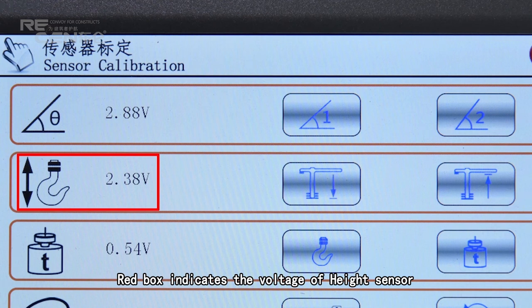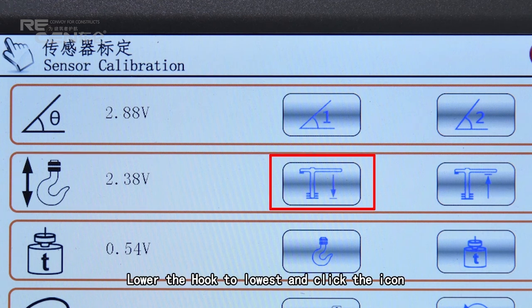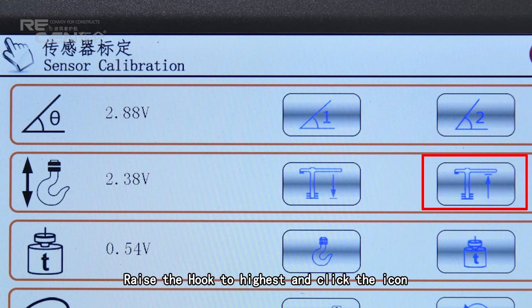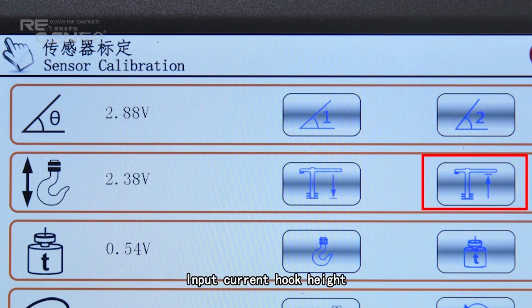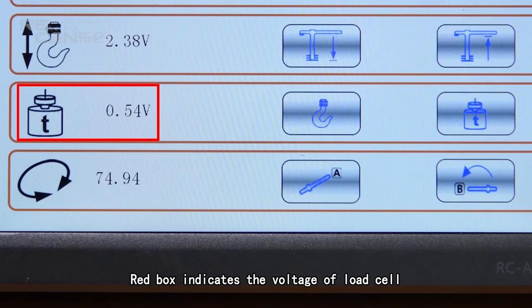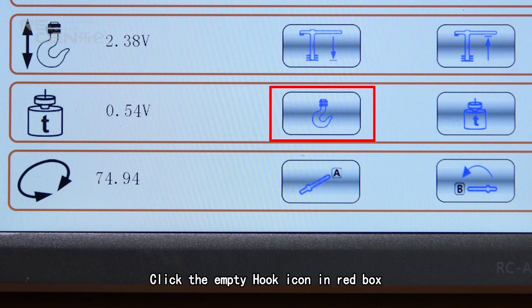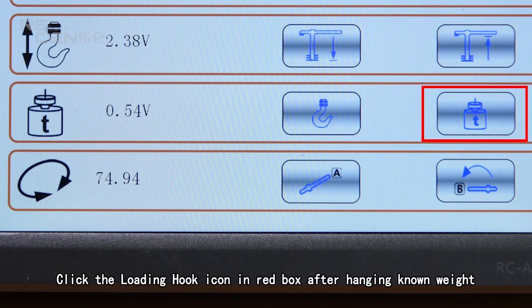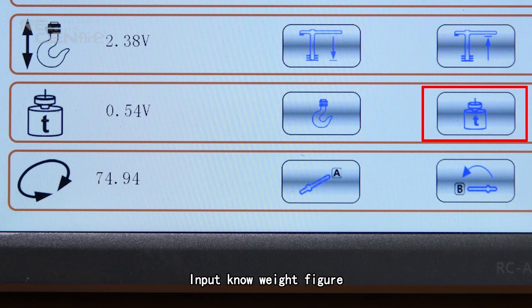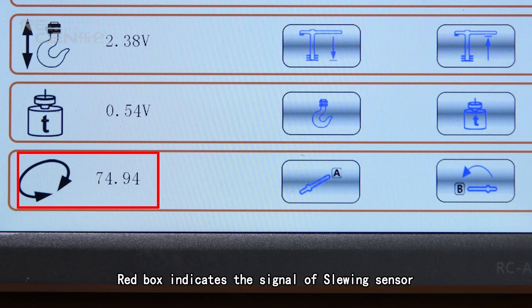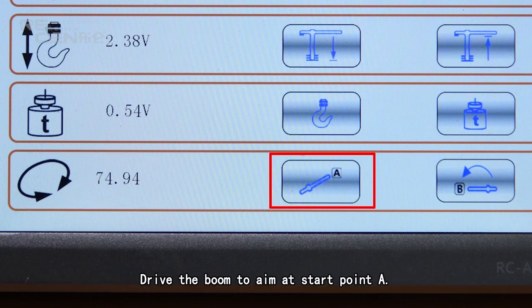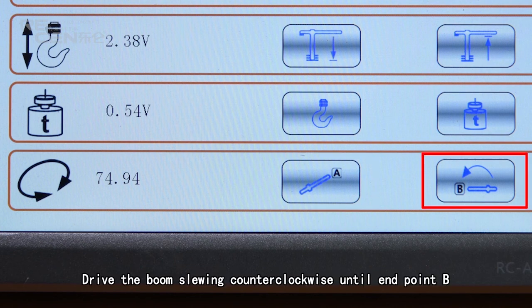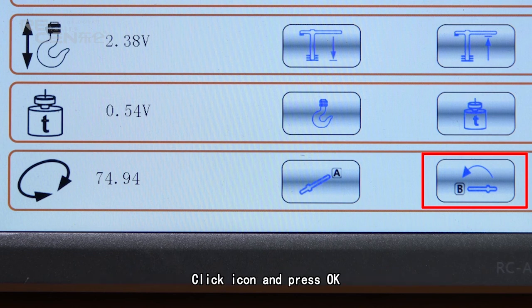The red box indicates the voltage of the height sensor. Lower the hook to the lowest position and click the icon; input the current hook height. Raise the hook to the highest position and click the icon; input the current hook height. The red box indicates the voltage of the load cell. Click the empty hook icon in the red box and input 0. Click the loading hook icon in the red box after hanging a known weight; input the known weight figure. The red box indicates the signal of the slewing sensor. Drive the boom to aim at start point A; click the icon and press OK. Drive the boom slowly counterclockwise until endpoint B; click the icon and press OK.